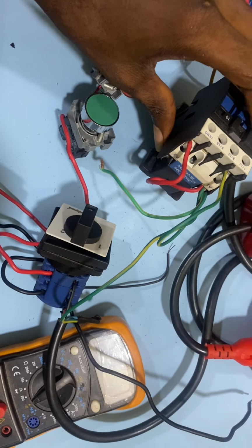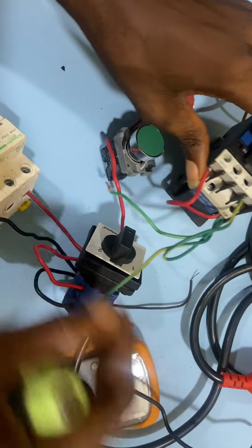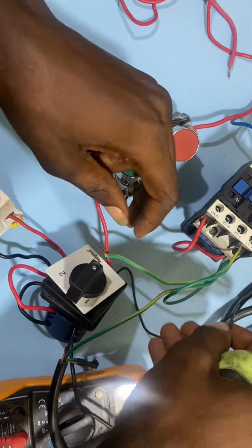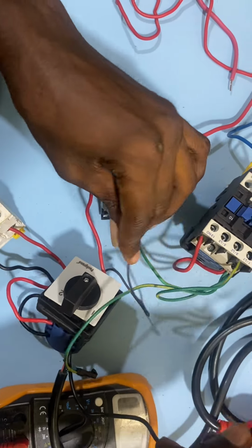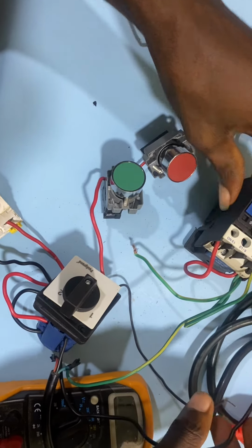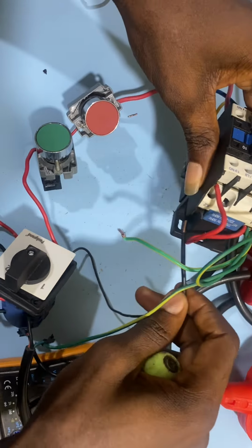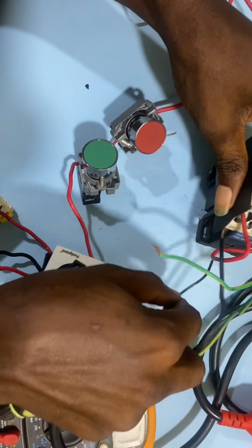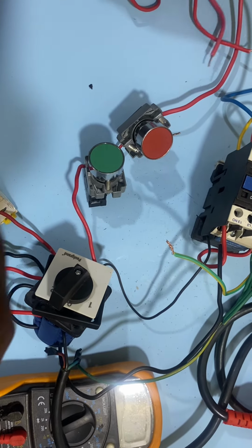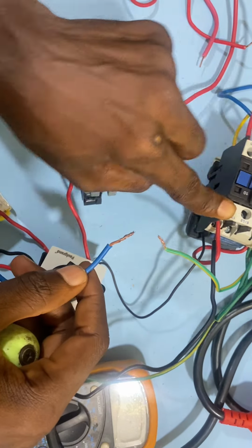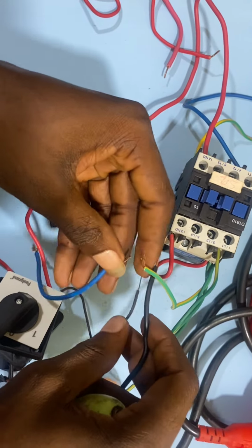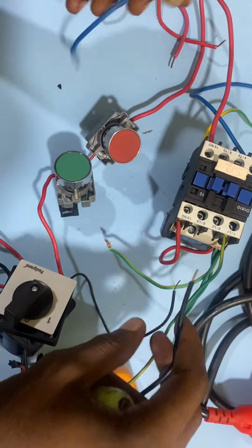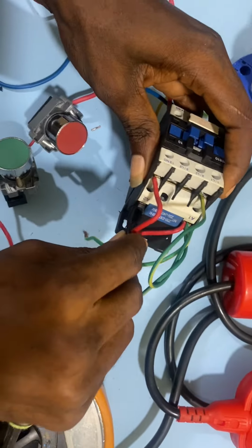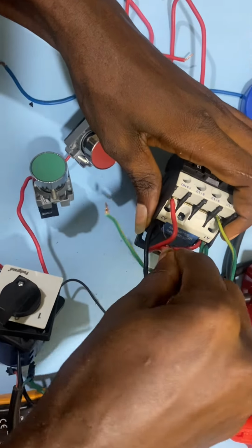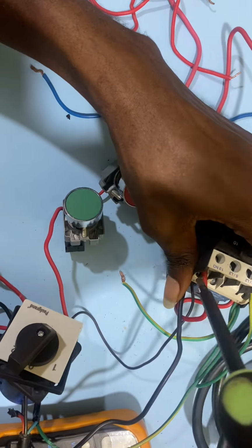So the next thing is to do the same to the neutral, and this was the neutral that was coming from the float from the selector switch, and this was another neutral. So all the neutral, I'm going to terminate it together. So let's do that together. This is my first neutral input, and this is my second neutral. So I'm going to connect this neutral also to L3. If I'm connecting it to L3, there is no need for that because I've already connected a neutral from A2 contact to the load from that other side of the contactor. So all I need to do now is to connect these two neutral together at this point. Alright, so I'm done with that connection.